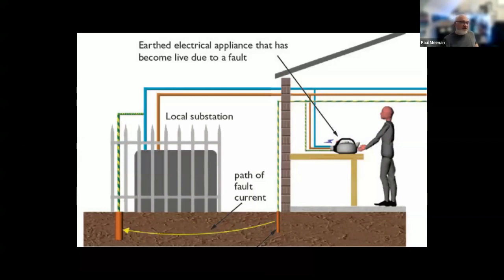Just to show you some simple pictures, this is how I learn. I'm a visual learner. There's a chap there standing in a building. The earthed electrical appliance, generally a kettle. If you're going to have a kettle that's metal and it becomes live or energized, somehow there's a breakdown in the proprietary insulation within the device or of the cable. That then allows a line conductor to come into contact with exposed conductive metalwork. And in theory, when that does, the energy will dissipate down the circuit protective conductor in a manner sufficient to allow the protective device to trip, down to the general mass of earth and off safely. So low impedance is very important for safety.